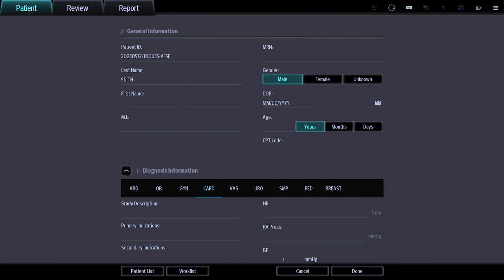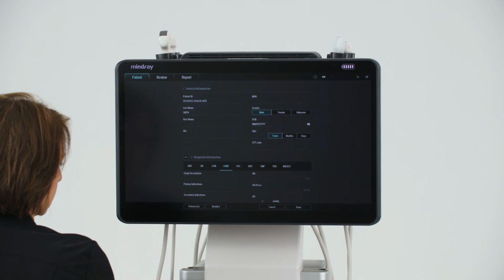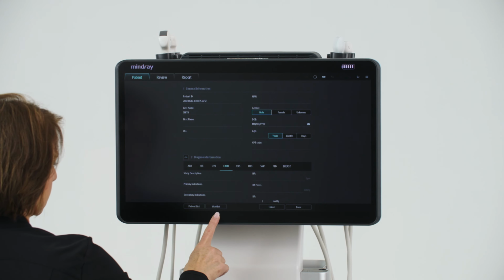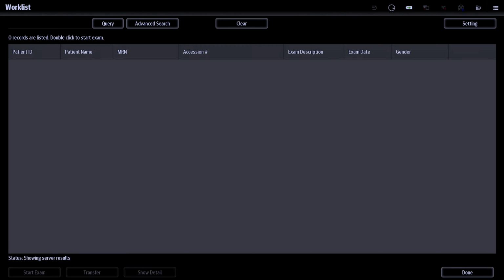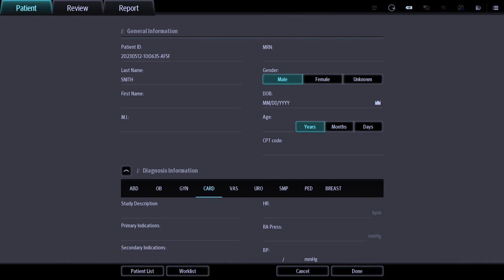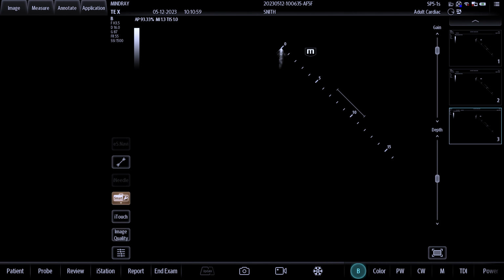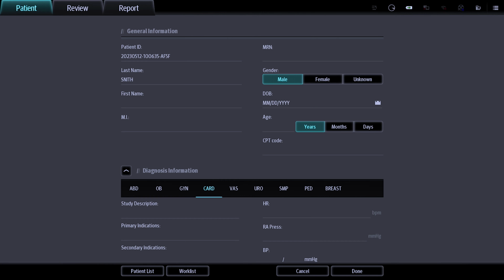A DICOM worklist or barcode scanner can also be used to enter patient information. If either of these options is selected, a clinical application specialist will configure these when the system is installed. To query a worklist, simply tap the Worklist tab along the bottom of the patient data screen. If this tab is grayed out, it is because you are still in an active exam. Exit the patient data screen, end the exam, and then return to the patient tab.